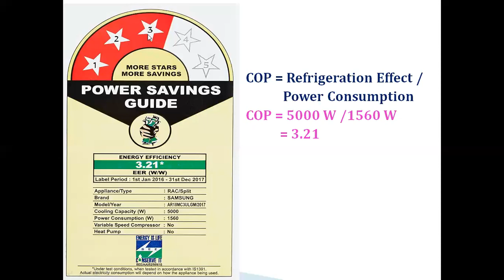Now we'll see. As per our definition, COP equals refrigeration effect divided by power consumption, right? Now what is the cooling capacity here? You can see that, 5000. And then what is the power consumption here? 1560. If we divide these two, then we get 3.21, which is used for this particular star rating. Because it is approximately around 3, they have given this star rating. That means here you can say power consumption is slightly more.